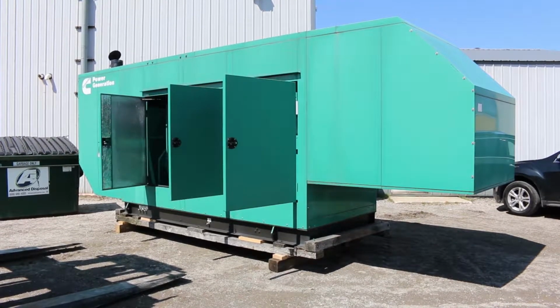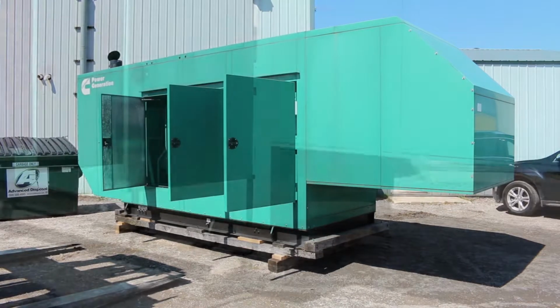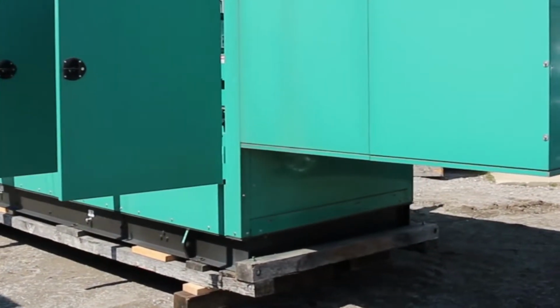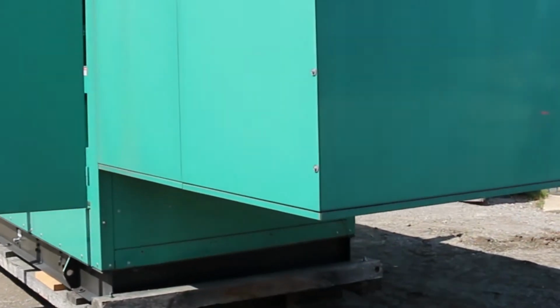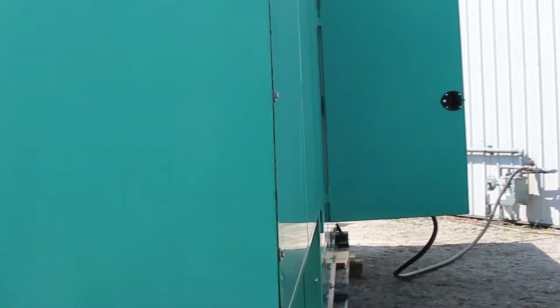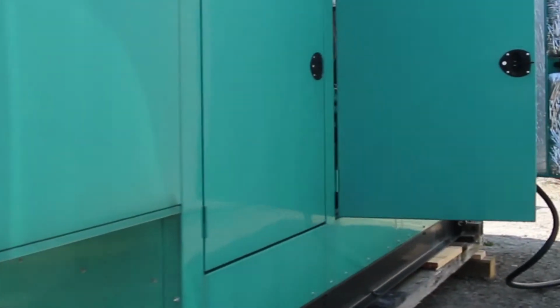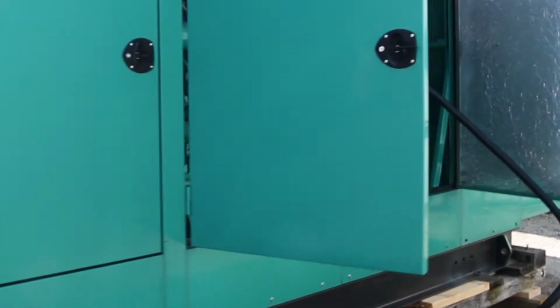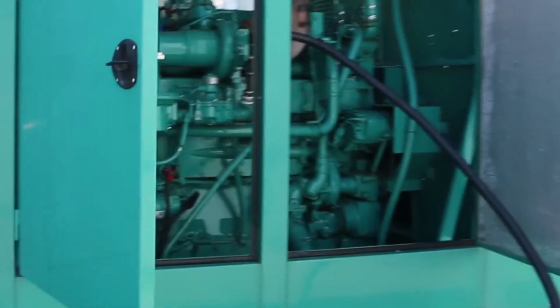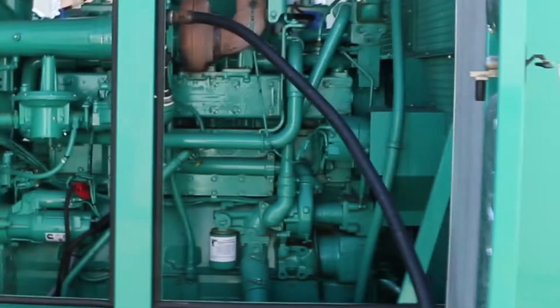Currently, the way it's set up, it has a 1200 amp Square D Masterpact electronic trip breaker. All the breakers in here are amazing. The 2 smaller ones I think are 800 amps apiece. I believe they're 600 volt breakers, so there's a very good chance we're going to be using the same breakers on the secondary side, but the main breaker will probably have to get switched from an amperage standpoint. That we won't do here in-house.